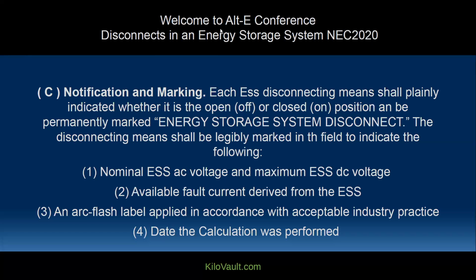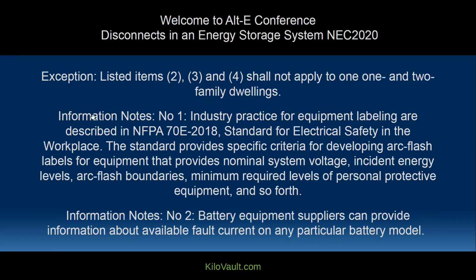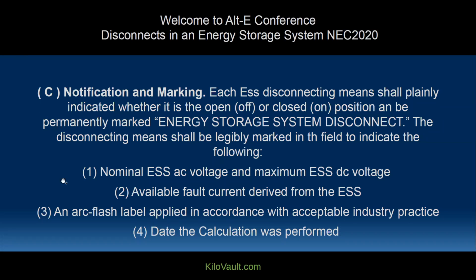So you said on this that it's only for 1 and 2 family dwellings, we only need number 1. Correct. So let me go to the next page. What's exempt is questions 2, 3, and 4 shall not apply to 1 or 2 family dwellings. So we go back. Pretty much the only thing they're really looking for is if it's an AC coupled energy storage, they want your nominal voltage for the AC, and if it's a DC coupled system, they're looking for the max voltage you're going to be reaching.